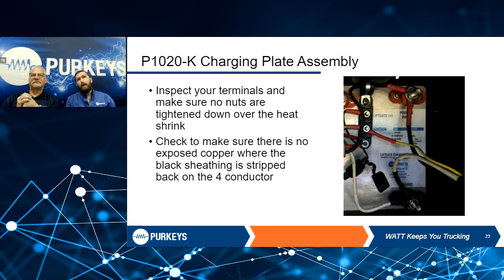After we've done all that, look for any kind of exposed copper, with this being on the underside of the trailer. Though a lot of these manufacturers make their battery boxes very well, there's always potential for water intrusion. And if water gets in and you happen to have a small cut into that copper wire, that's where corrosion starts to build up.